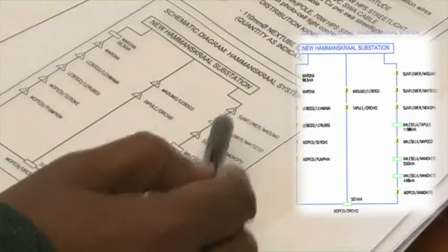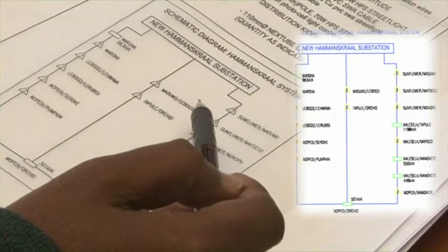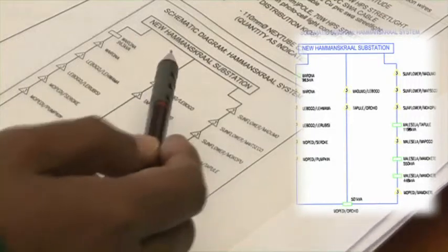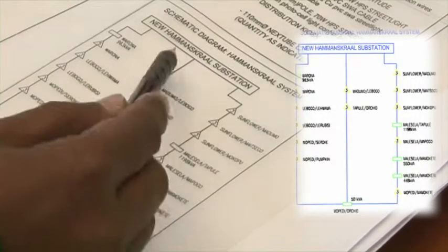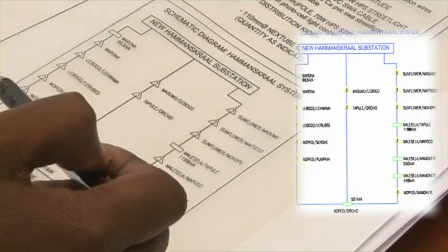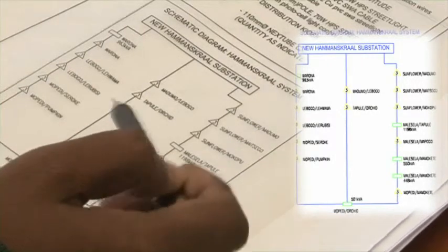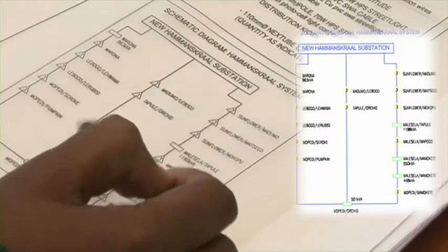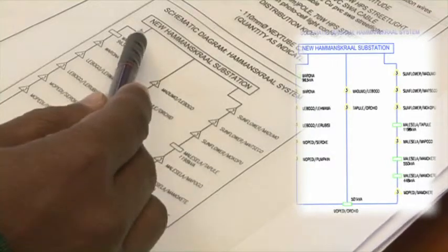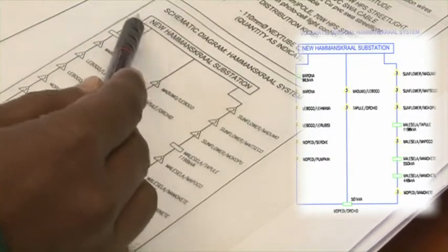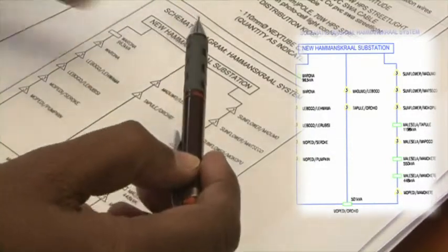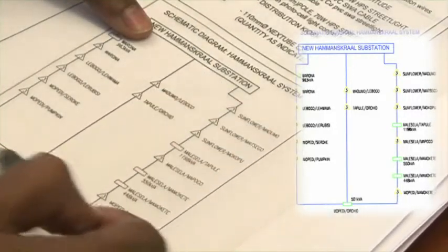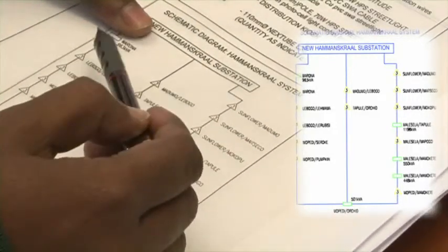They ring into each other to give you security of supply, so that if you have a problem on one leg, you can feed back on another leg. So your design has to make sure you allow enough capacity on the cable. Worst case, you have a fault here, that piece of cable goes down, meaning it's open, and you've got to feed all the way back there, picking up all that load.